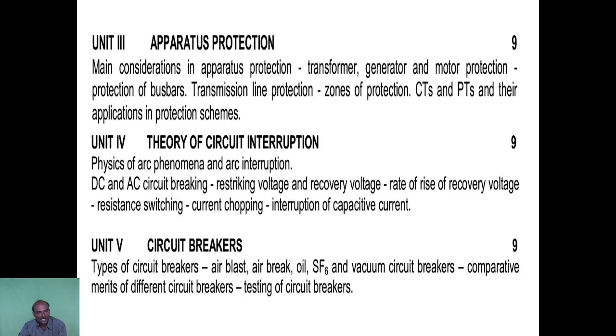The arc phenomena, mainly the arc phenomena, DC and AC circuit breaking, the various technologies, restriking voltage and recovery voltage, rate of rise of recovery voltage, resistance switching. These are all about theory of circuit interruption. Then Unit 5 discusses about circuit breakers. So mainly different types of circuit breakers. Based on the medium used, we have air blast, air break, oil, SF6 and the vacuum circuit breakers.